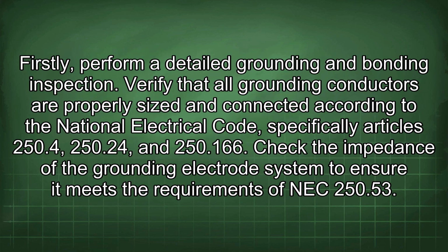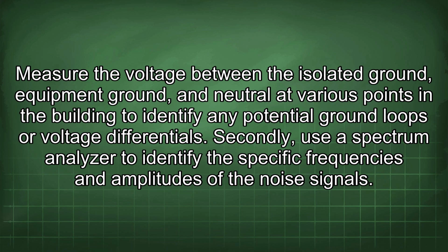Firstly, perform a detailed grounding and bonding inspection. Verify that all grounding conductors are properly sized and connected according to the National Electrical Code, specifically Articles 250.4, 250.24, and 250.166. Check the impedance of the grounding electrode system to ensure it meets the requirements of NEC 250.53. Measure the voltage between the isolated ground, equipment ground, and neutral at various points in the building to identify any potential ground loops or voltage differentials.